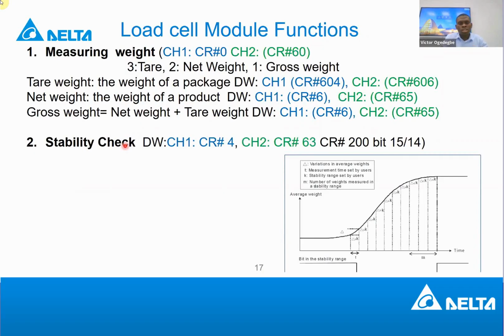Stability: once you have set up the module, I want to check if your measurement is stable. There are some flags. I showed you this register before, control register 200. There are some flags there you can monitor to see if what is coming from the sensor, what is being read, is stable. How does that happen? In the control register for channel 1, control register 4, you specify the range of the value of the weight you want to measure. When we talk about the weight, there is an analog value coming from the sensor. There's a digital value corresponding to that analog value in the load cell module. The load cell module only gives you digital values 1, 2, 3, 4, 5, 6, 7, 8. But the load cell or the sensor itself gives you voltage. So the load cell module gives you the equivalent of that voltage in digital format.